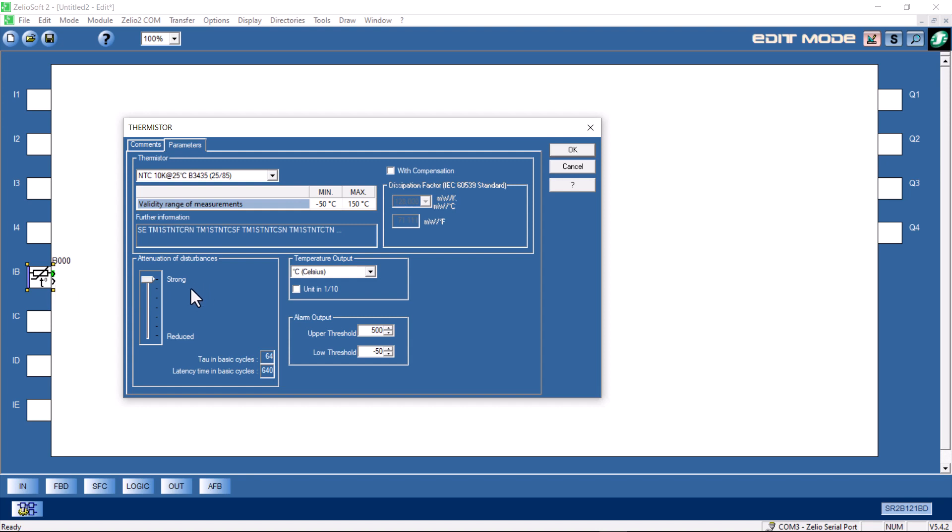To the left of it, we have what's called an attenuation of disturbances setting. Basically, it's a filter on the input. We can filter if you get some spikes, some magnetic induction on the conductors, and you have a rise and fall in the voltage. You can ignore them based on these values. I'll just leave it on strong as per the default. And we're good to go. I'll click OK.